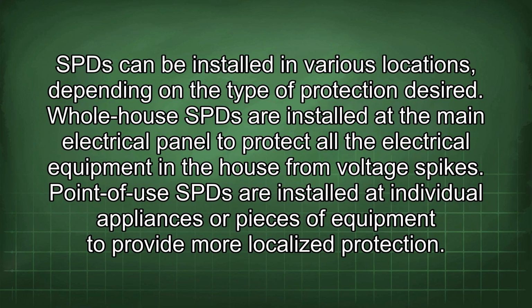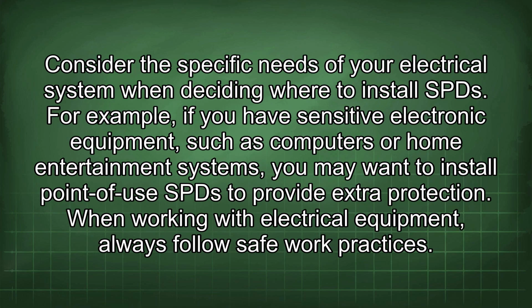SPD can be installed in various locations depending on the type of protection desired. Whole house SPD are installed at the main electrical panel to protect all the electrical equipment in the house from voltage spikes. Point of use SPD are installed at individual appliances or pieces of equipment to provide more localized protection. Consider the specific needs of your electrical system when deciding where to install SPD. For example, if you have sensitive electronic equipment, such as computers or home entertainment systems, you may want to install point-of-use SPD to provide extra protection.